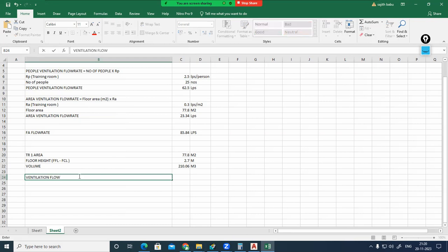Ventilation flow with respect to the air changes method is equal to the volume of your space that you are designing in meter cube, multiplied by air changes per hour, divided by 3600. When you are doing this calculation, because volume of space into air changes per hour, you will be getting the value in meter cube per hour only. So this meter cube per hour, if you are dividing with the 3600, you can convert that into meter cube per second. So this meter cube per second value, when you are multiplying with the 1000, you can convert that into liter per second. You'll be getting that in liter per second.